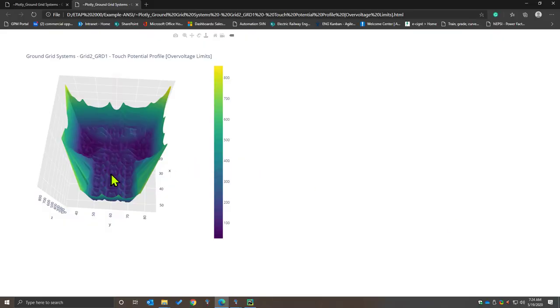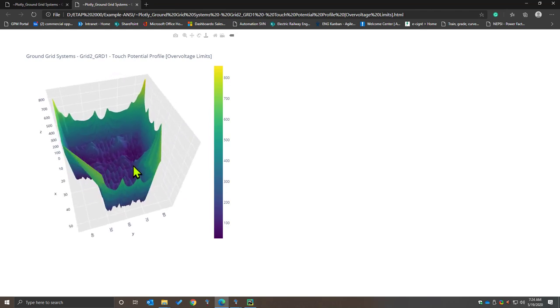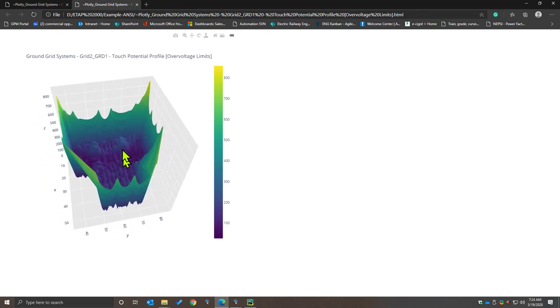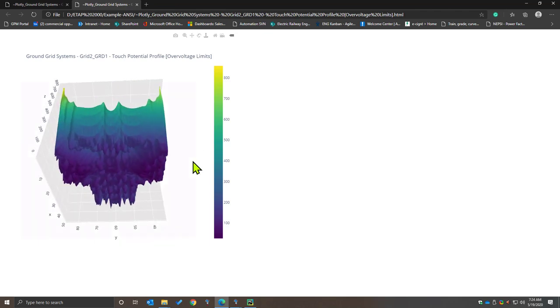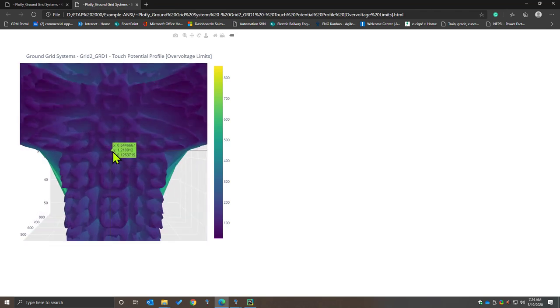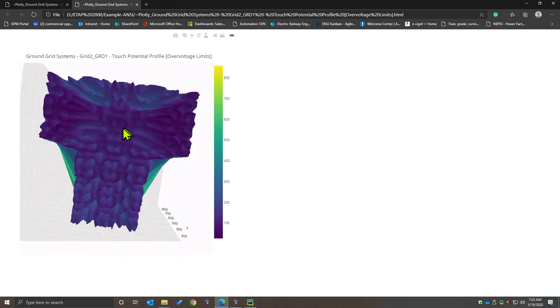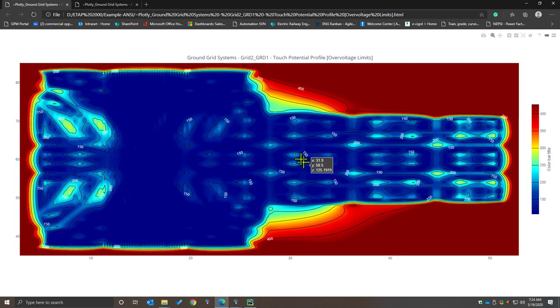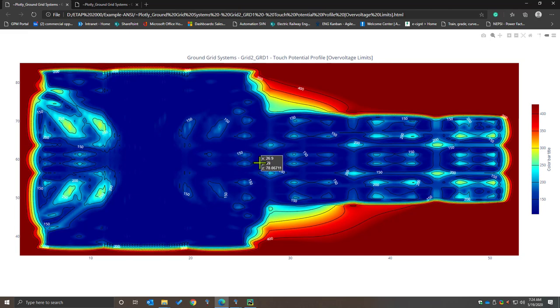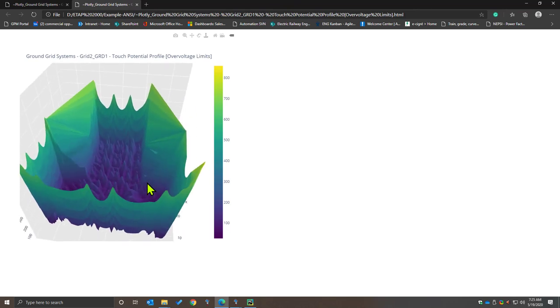By changing the plot preferences, you can also allow ETAP to utilize built-in or provided Python scripts to export the ground grid data into Python-based charting packages and visualize the same information in a browser-based rendering or any other renderer provided in the plotting package. In this case, we are plotting the touch potential profile in 3D visualization or a 2D contour where you can evaluate the X, Y, and Z coordinates of your ground grid system. ETAP provides the ability to use the PlotView for 2D and 3D charting, and also use built-in Python scripts to export and visualize data into a Python-based visualization library.